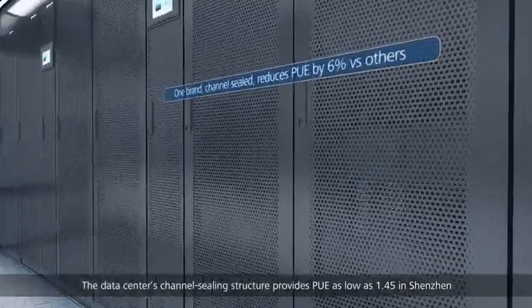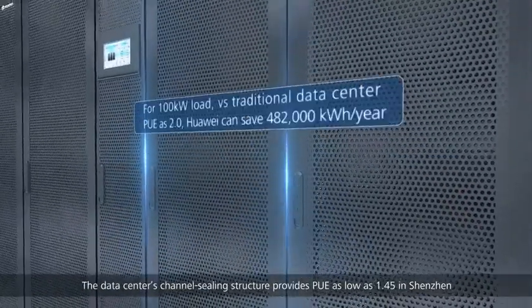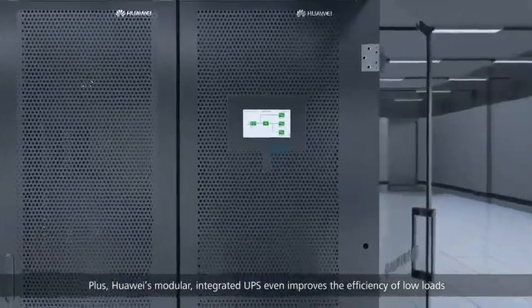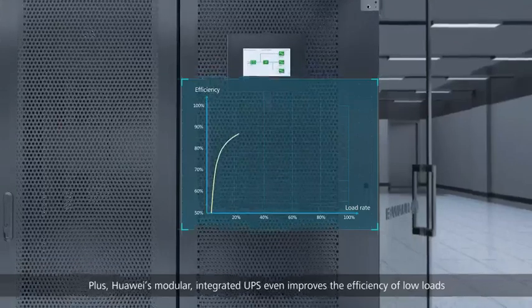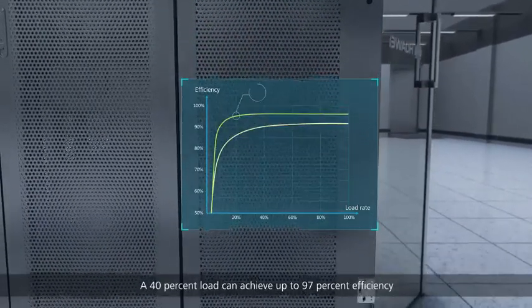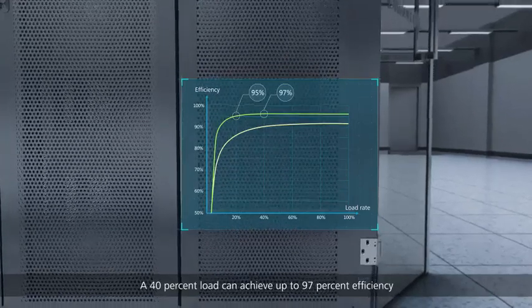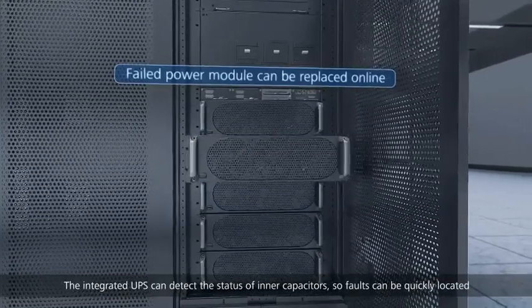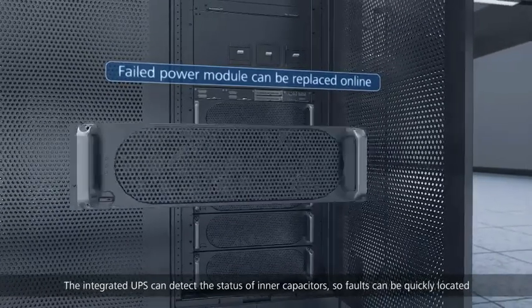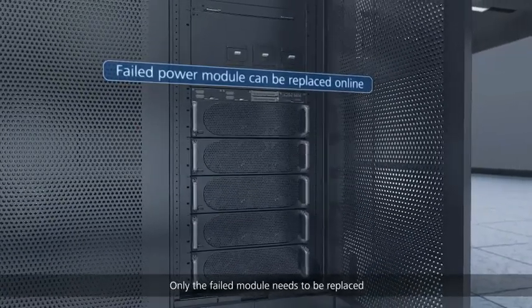Any node fault will not affect normal power supply and signal transmission of smart sensors. The data center's channel-sealing structure provides a PUE as low as 1.45 in Shenzhen. Plus, Huawei's modular integrated UPS improves efficiency even at low loads — a 40 percent load can achieve up to 97 percent efficiency. The integrated UPS can detect the status of inner capacitors so faults can be quickly located and only the failed module needs to be replaced.